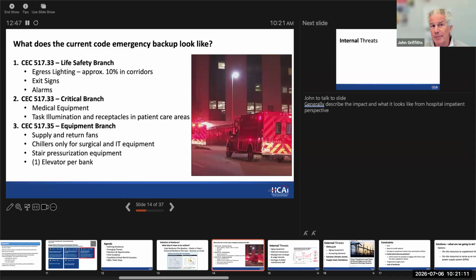When these power outages happen in California, it's often during the hottest time of year, yet you only have chillers cooling for surgical suites and IT equipment. Then there's stairwell pressurization—not many high-rise buildings, but it's there too—and only 1 elevator per bank by code, so you don't have full elevator backup. That's code minimum.